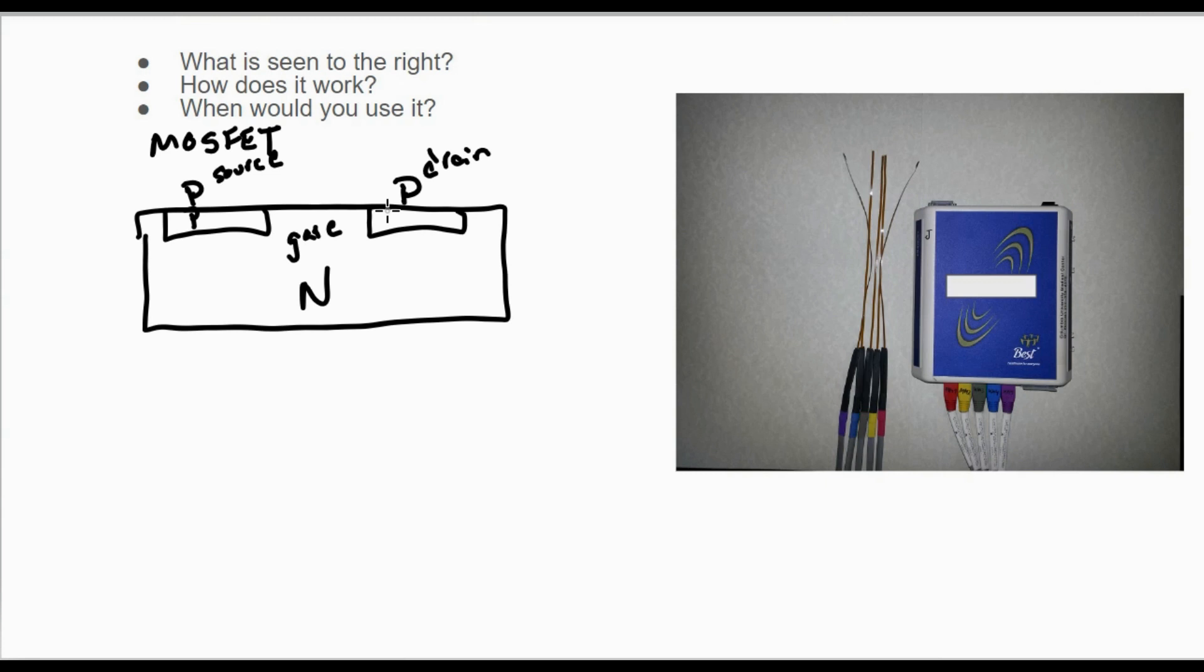In radiation oncology, we only use the P-type, meaning that the source and the drain are P-types, the substrate is an N-type, and the gate voltage that we are monitoring is negative. The threshold voltage needed will increase with the dose that this receives, so you can relate that threshold voltage to the dose.